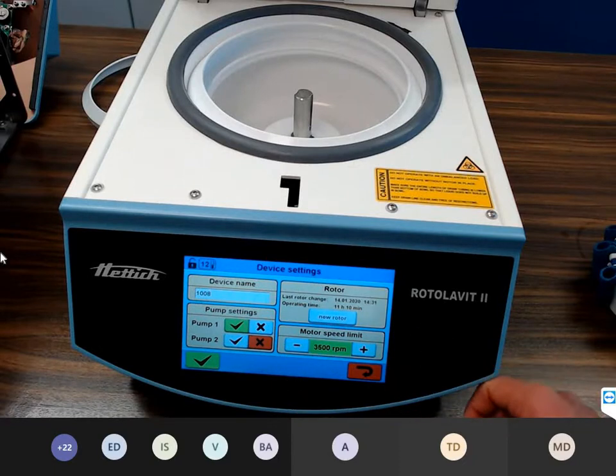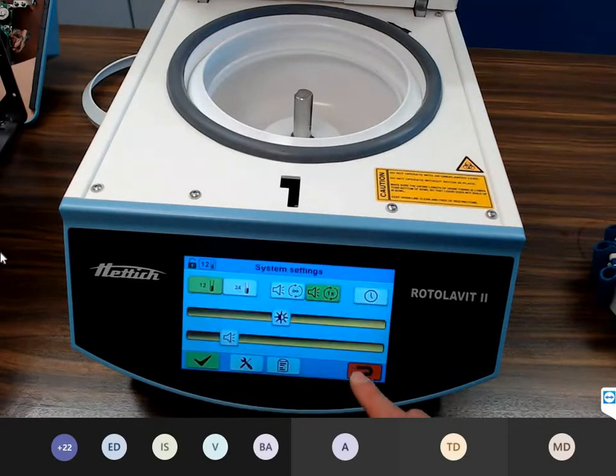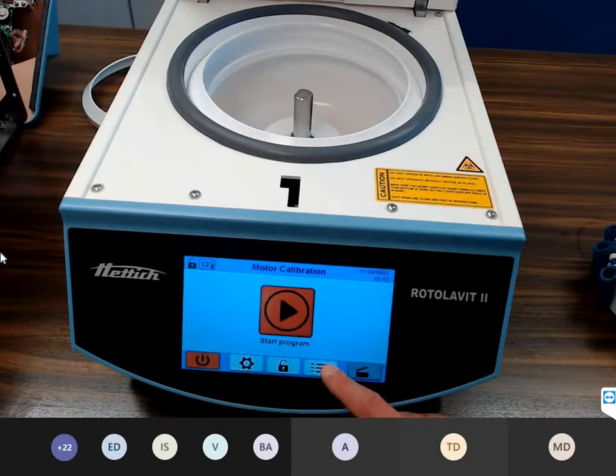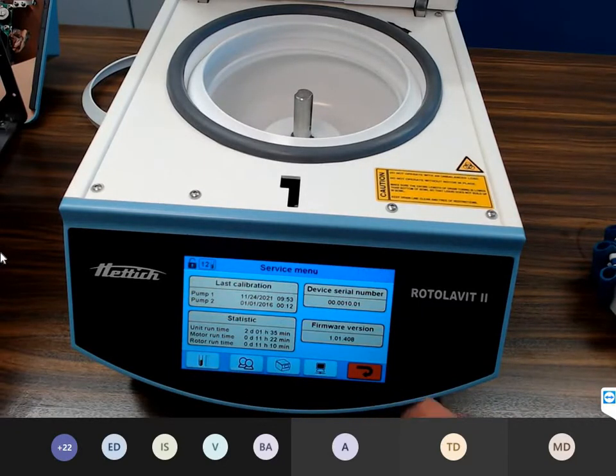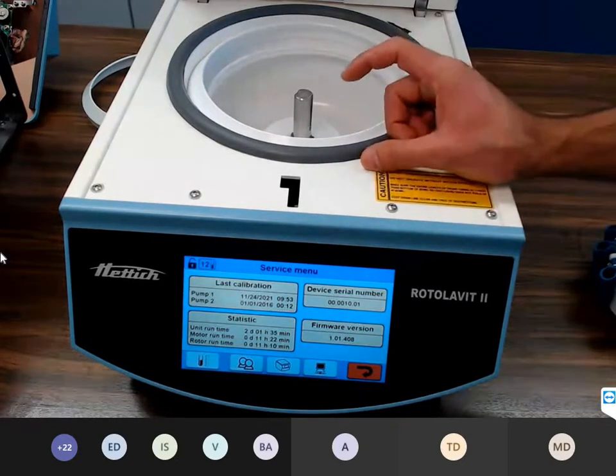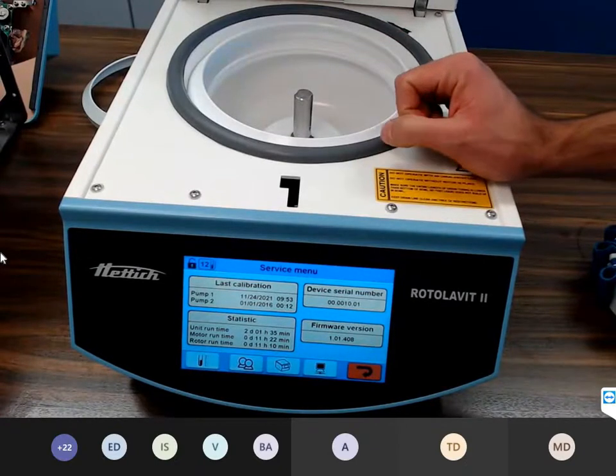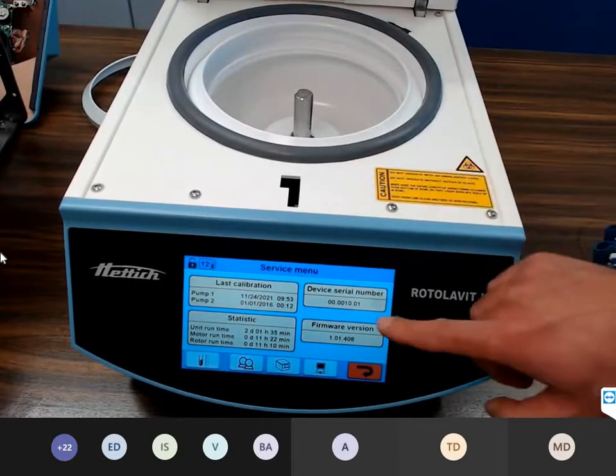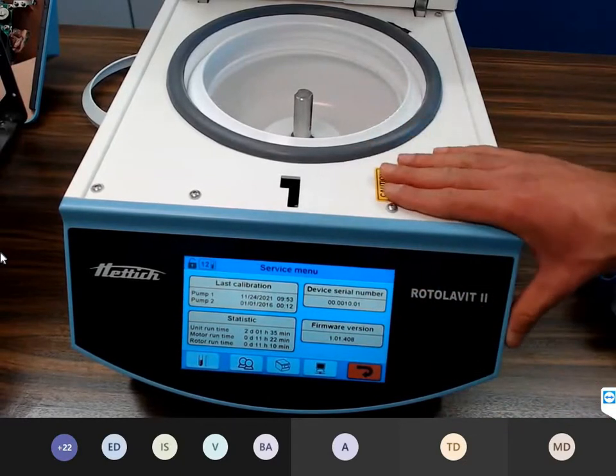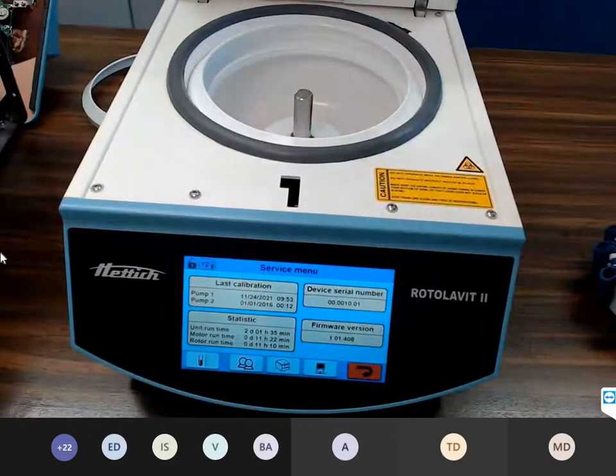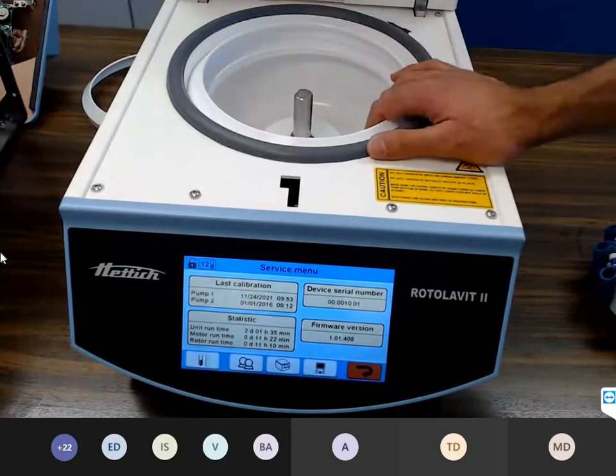After the motor calibration, set the maximum RPM again. Choose a program. And that's it. So, maybe one important thing: if you replace the CPU board, we have to set the serial number on the device. Very important, because the CPU board is without the serial number.